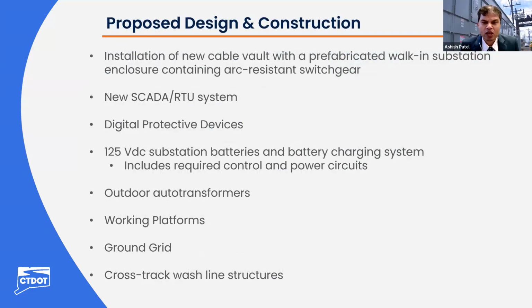Next, I'll be discussing the common design and construction steps involved in designing the balancing substation from start to finish. We will see the actual site location in a moment. The proposed site location is critical for construction of the balancing substation. Connecticut DOT and Metro North adopted implementing the design of arc resistant switchgear under medium voltage application. We have been designing prefabricated walk-in type arc resistant substations for balancing substations, supply substations, and signal substations under the New Haven main line power program.